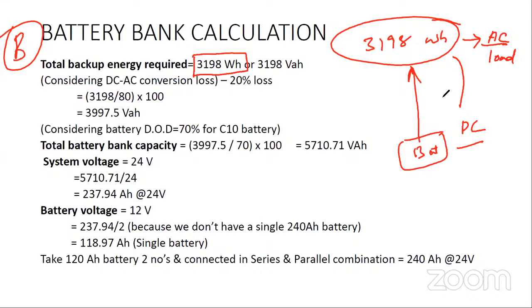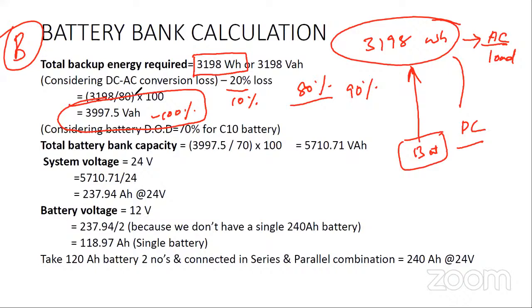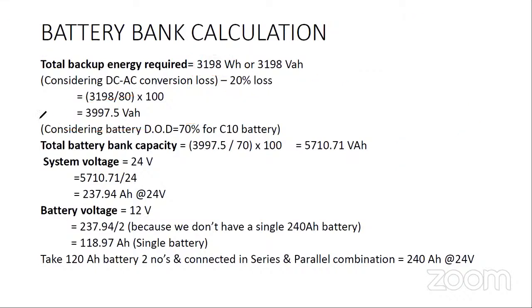So considering the DC to AC conversion losses, I'm taking 80% inverter efficiency as a worst-case analysis. If you have a 90% inverter efficiency, then the loss, instead of 20%, is going to be 10%. So I'm taking my worst-case calculation. 3198 divided by 80 into 100 gives my 100% of the energy, which I need to take from the battery to provide backup for the entire load as designed. This is the first conclusion.